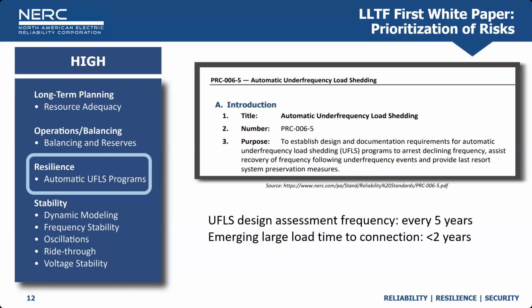When we don't have sufficient reserves in the under-frequency sense, we do have this under-frequency load shedding safety net. So the under-frequency load shedding assessment is done every 5 years as required in PRC 6. The large load time to connection is less than 2 years, and so we can have a significant amount of demand that is increasing within our system, while our under-frequency load shedding schemes are designed or reassessed every 5 years for that system.